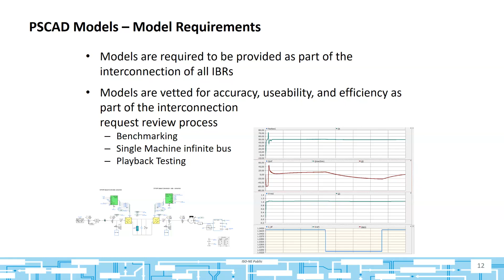Let's go to the next slide, and I think we're going to move over to the performance testing of the actual capabilities of the machine that is being installed. So we do have a power factor demonstration where it's required that the device absorb and produce the maximum reactive power capability until a defined limit is reached, and we're looking for that limit and limitation, and what is causing it and what the extent of the limitation is. We're looking for maximum excitation limiters, under excitation limiters, volts per hertz limiters, terminal voltage limitations, or procedural limitations, as they are manifested in the equipment.